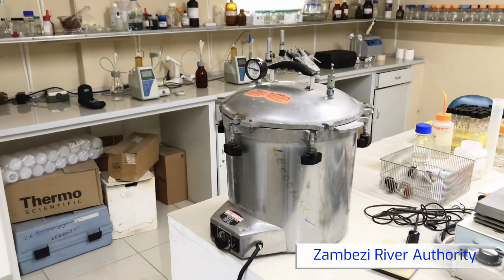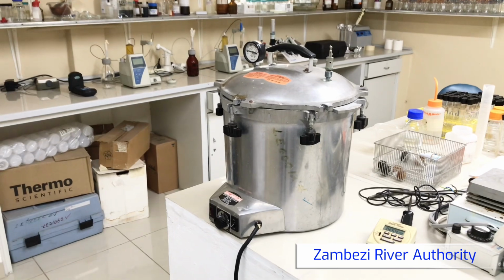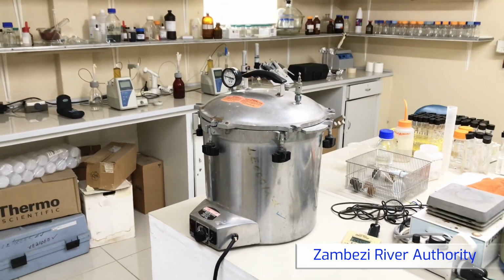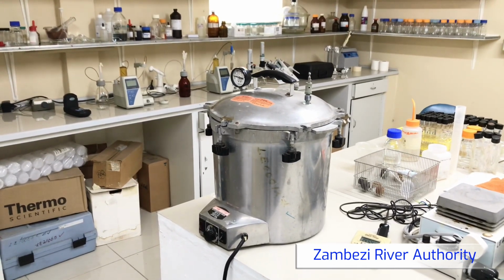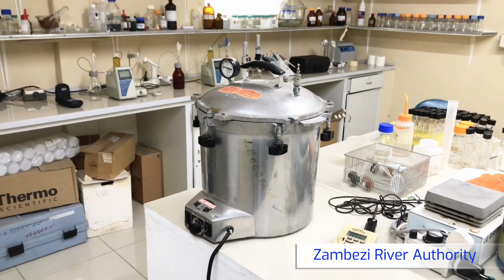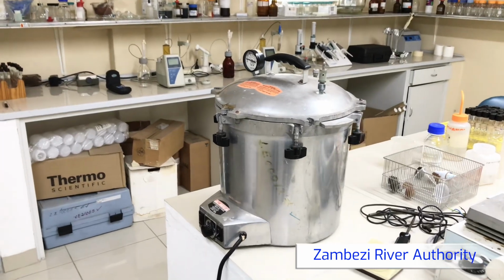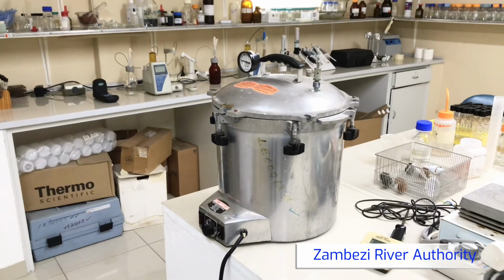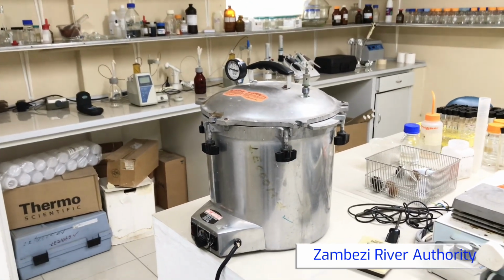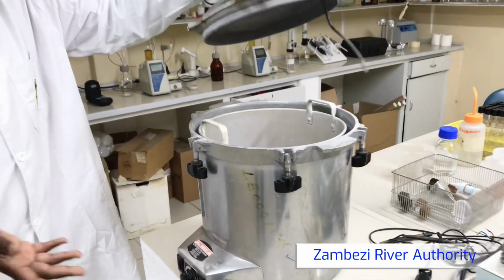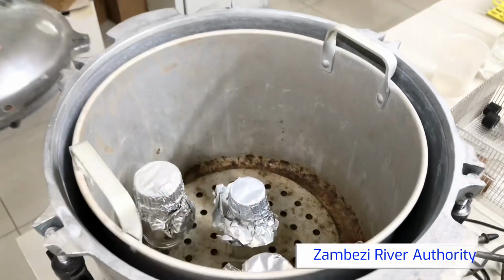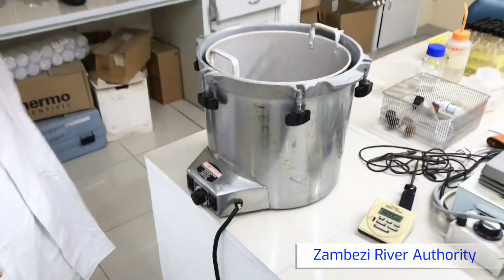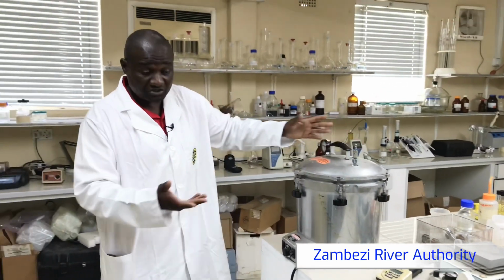We've got an autoclave. We use it for sterilizing sampling bottles meant for bacteriological sampling. As you might be aware, bacteria is found everywhere. So we want to make sure that the sampling bottle you are using for sampling, let's say fecal coliform, is free of viable organisms. It's similar to a pressure cooker; it runs at high pressure and high temperature. Other than sterilizing our sampling bottles, we also use it for digestion of samples, such as if we are doing total phosphorus, total nitrogen. So apart from using the block digesters, you can also use the autoclave.